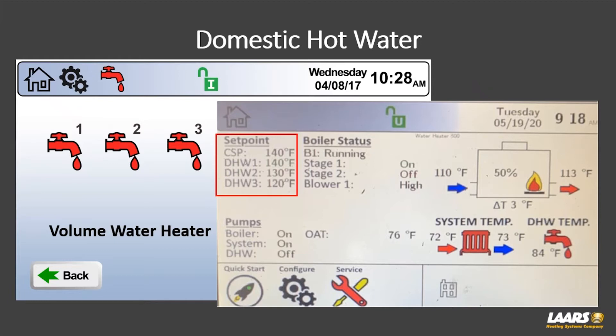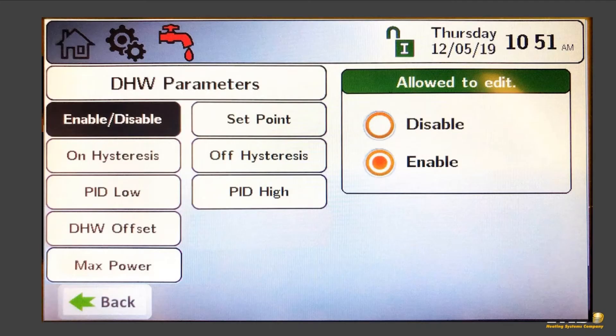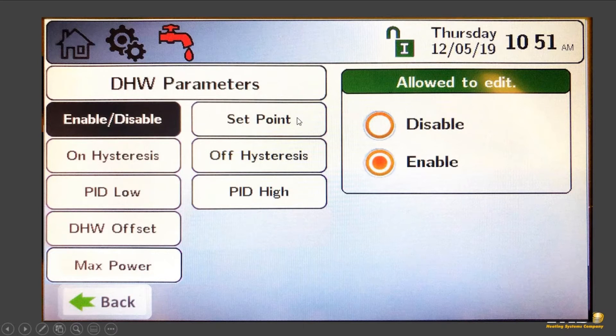DHW3 gives you more options. We provide a sensor that can go out into the tank. Under configuration, one of the DHW screens allows you to enable or disable any one of these parameters such as DHW2. Your set point — click on it, go in, and choose your value, for example 140 degrees. You've also got your on and off differentials to set up.